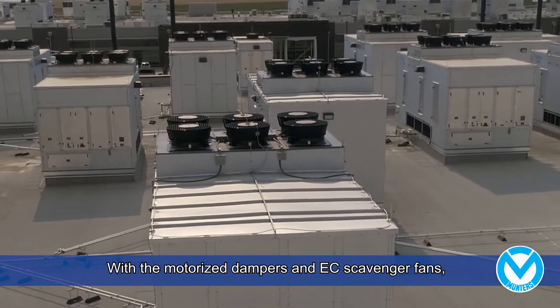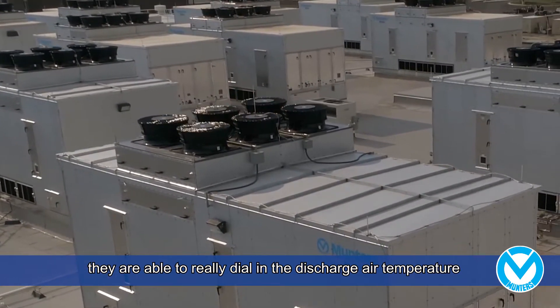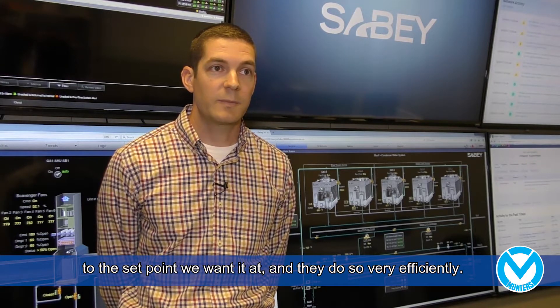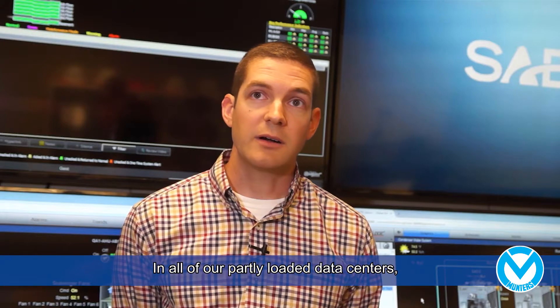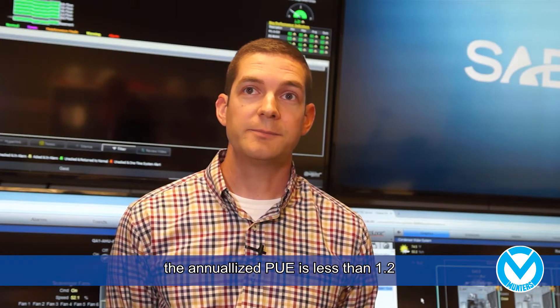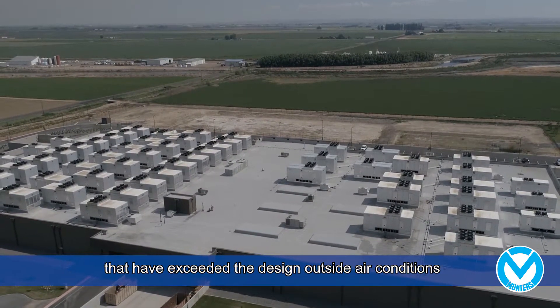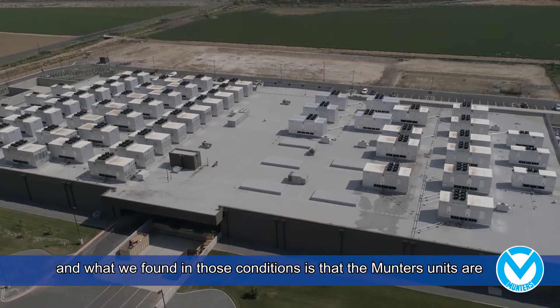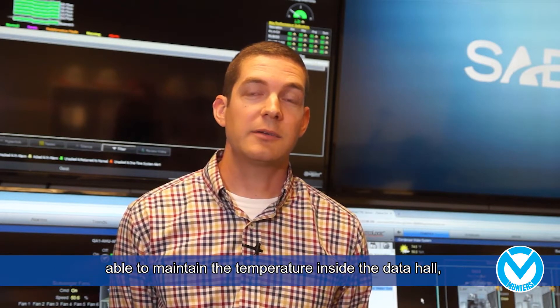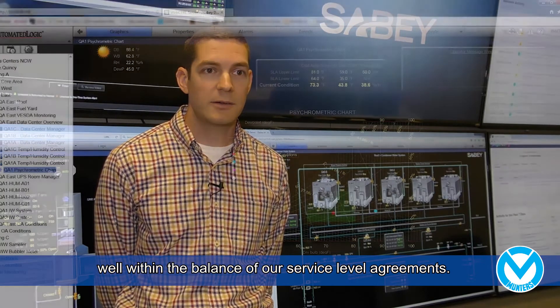With their motorized dampers and EC scavenger fans, they're able to really dial in the discharge air temperature to the set point that we want it at, and they do so very efficiently. In all of our partly loaded data centers, the annualized PUE is less than 1.2. We have experienced both summers and winters here in Quincy that have exceeded the design outside air conditions, and what we found is that the Munters units are able to maintain the temperature inside the data hall well within the bounds of our service level agreements.